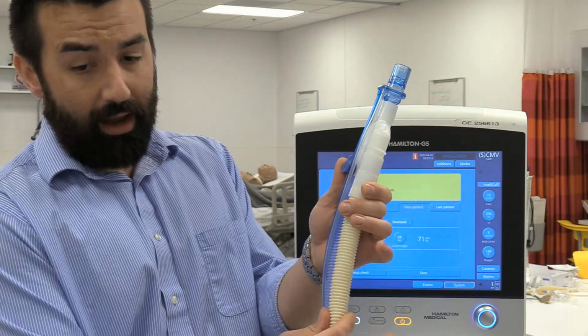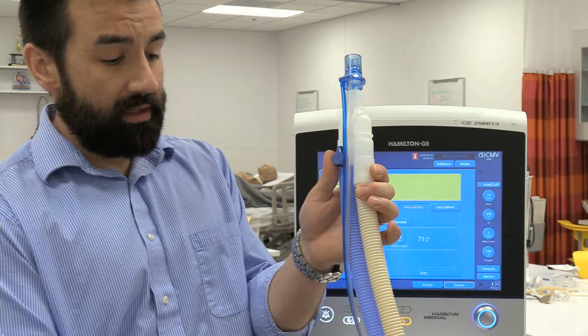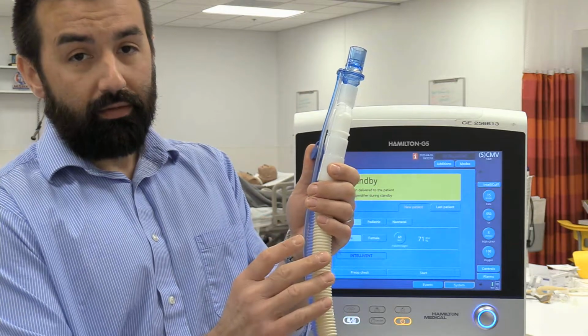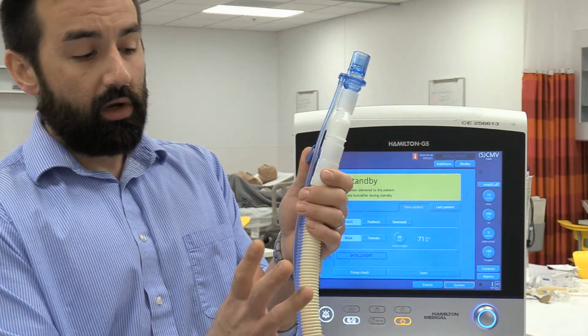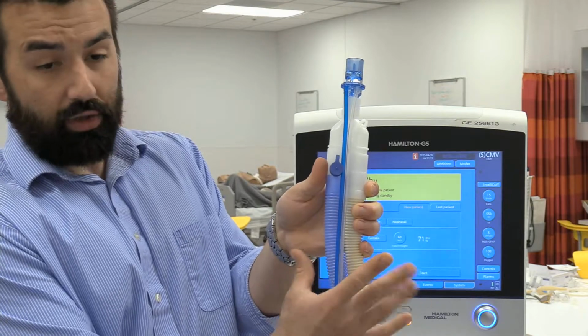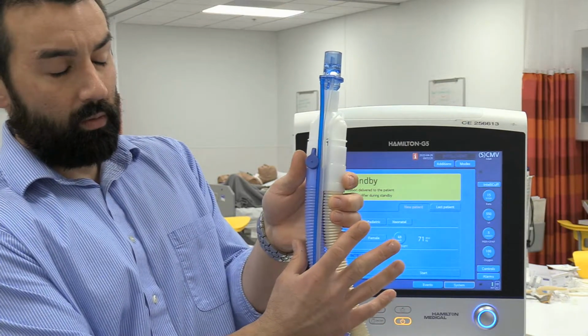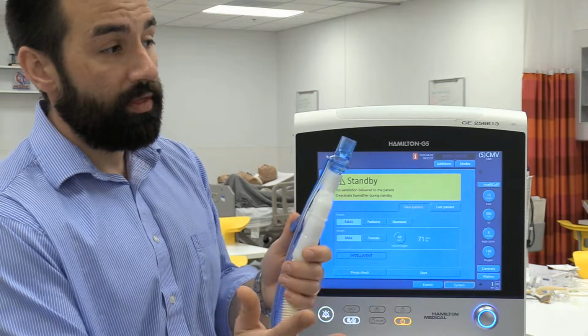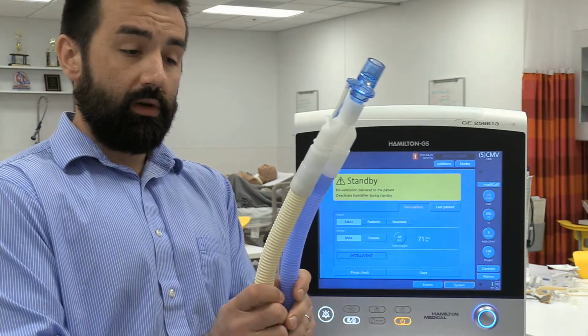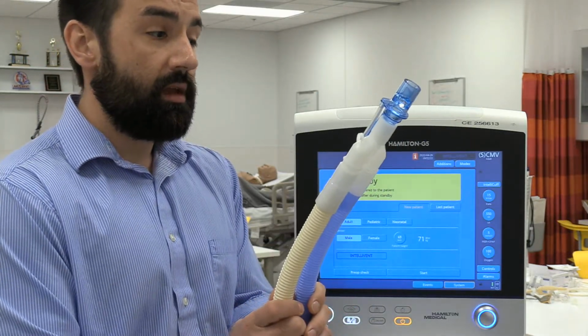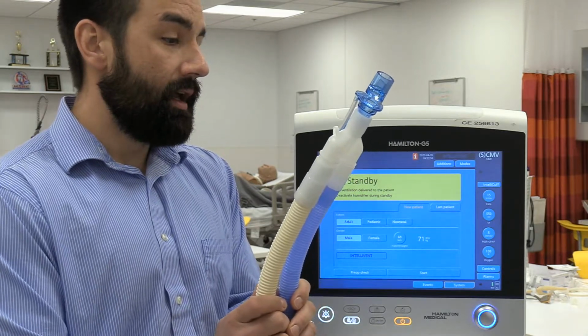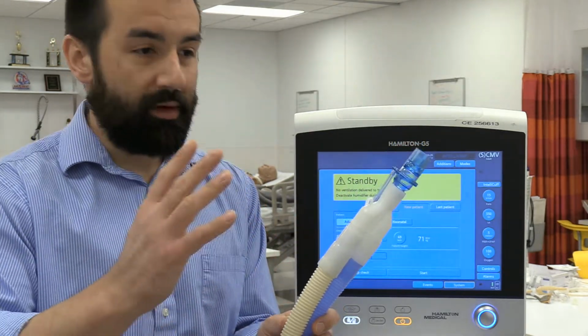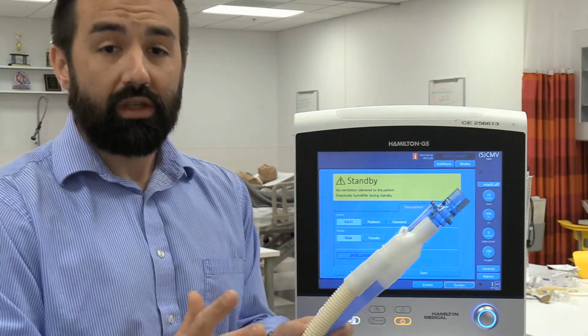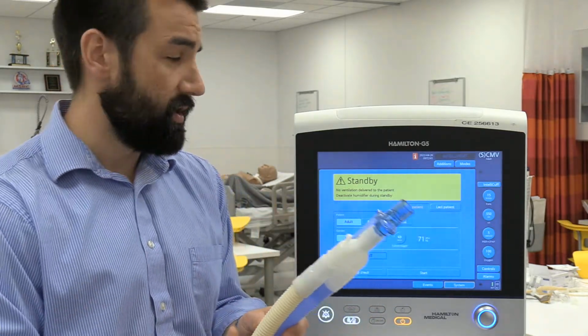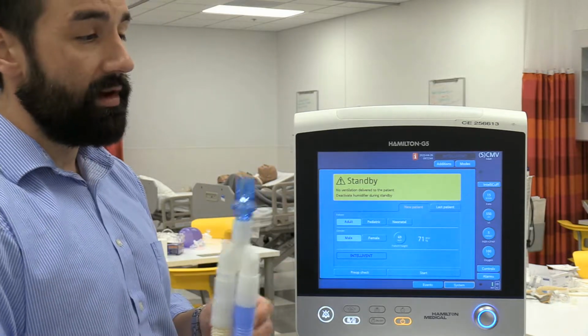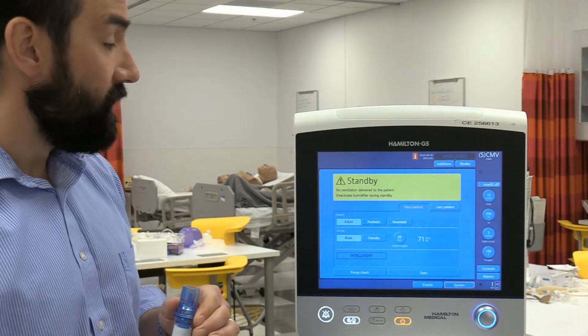Our circuits, not being made out of a rigid material, are going to lose a little bit of the volume that's supposed to go to the patient as the circuit is pressurized, okay? We don't want that volume loss to occur, so we want the ventilator to figure out how many mLs per centimeter of water are lost with each breath. Behind the scenes, if we set a tidal volume of 500, it might give a little bit more, but it ensures that the patient really gets what we set, which is what we want to take place. Most ventilators do this. There are some out there, especially transport vents, that do not.